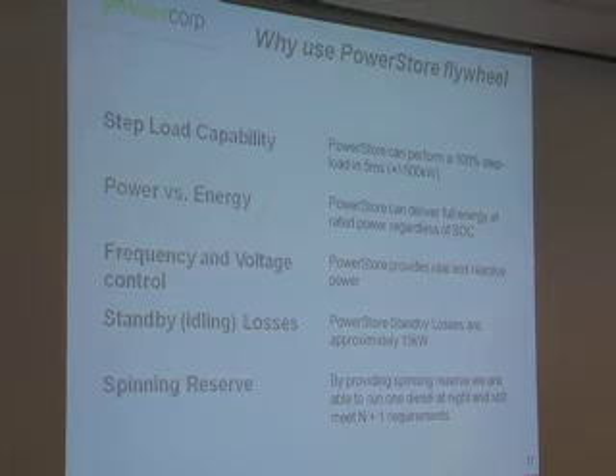So why were we using the flywheel? I touched on it briefly, but the step load capability to catch the solar if it tripped offline, but also if one of the diesels went offline, it gave us that comfort that we could carry the spinning reserve in the flywheel and not have to run extra diesel generation. On power versus energy, the power store can deliver full power regardless of its state of charge. So if it's at say 40% state of charge, it can absorb or source 500 kilowatts for the rest of that state of charge. We have set points whereby we'll get down to a minimum state of charge, and then we'll have to bring on other diesel generation so the flywheel doesn't run out of power.